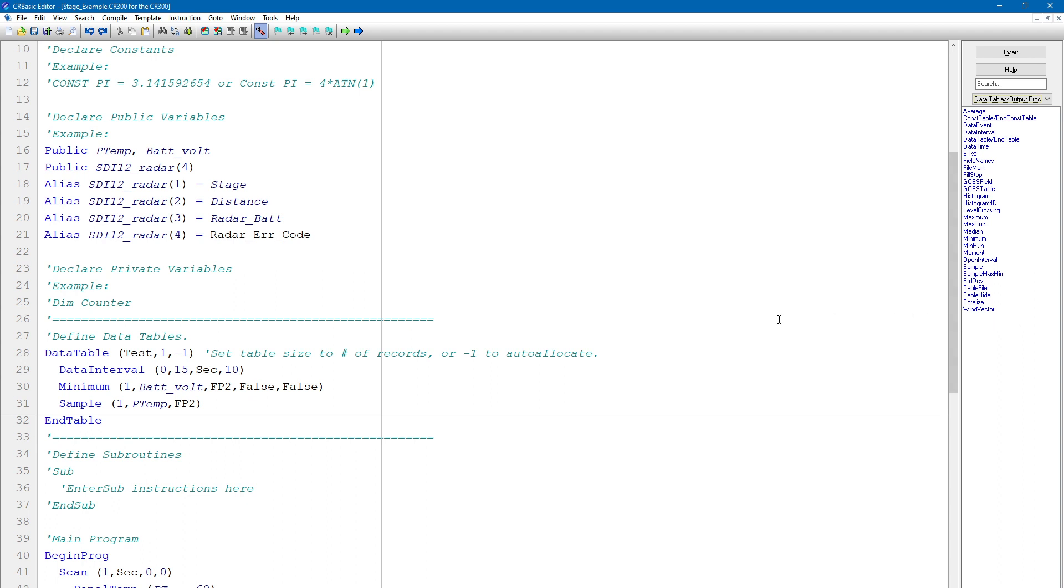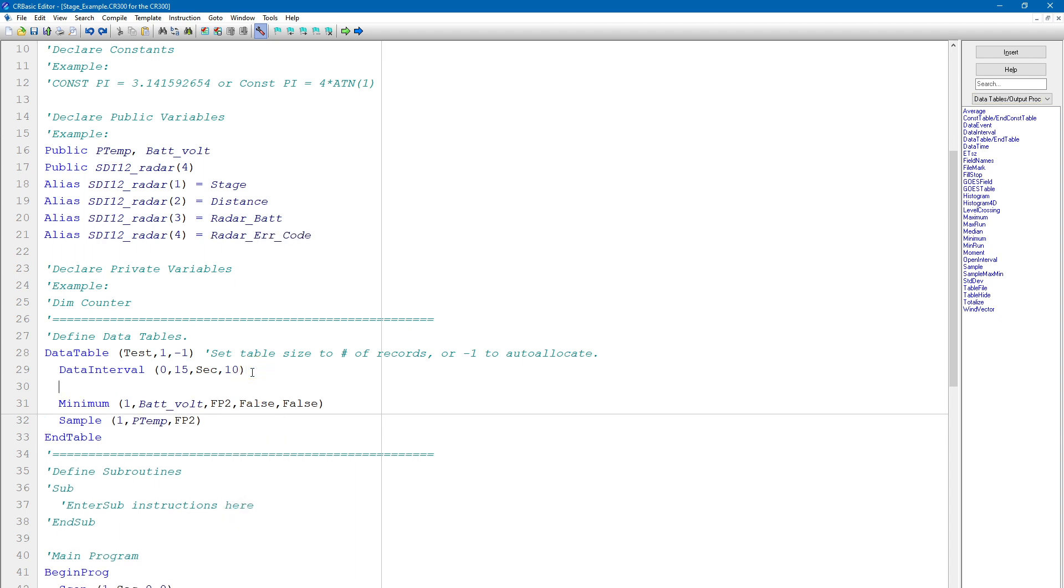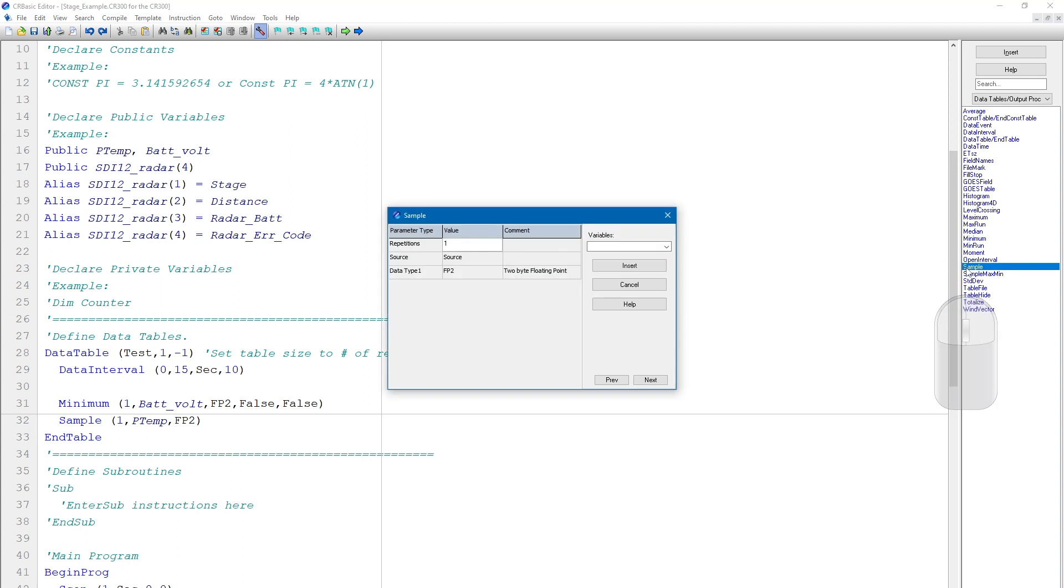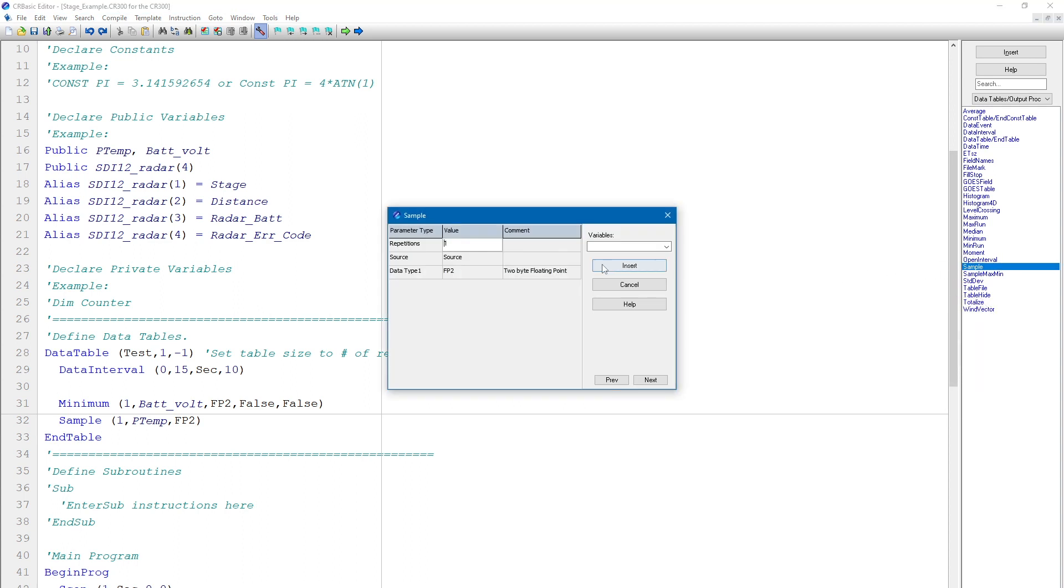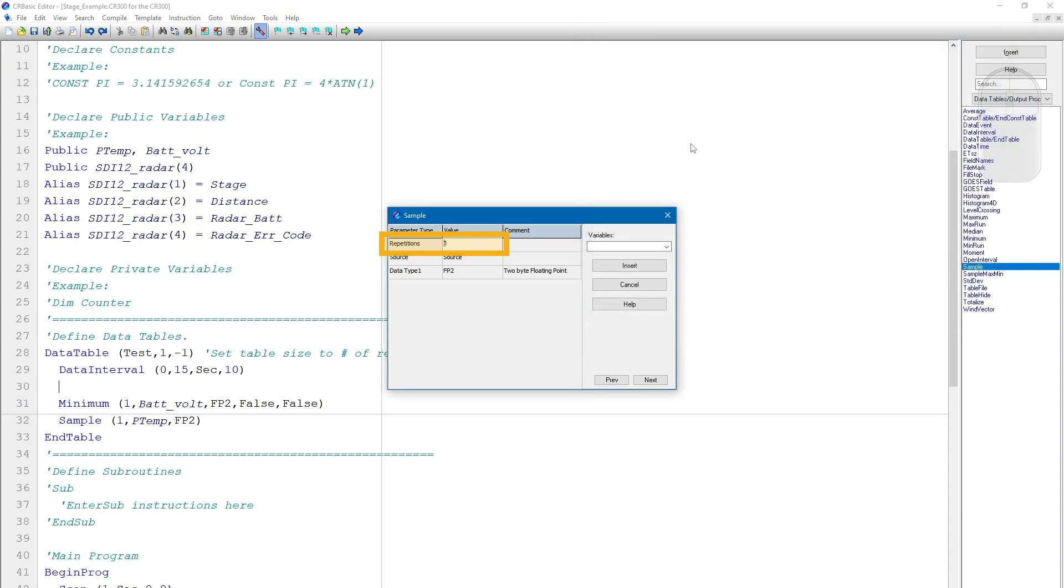So the first output I add to this data table is a sample of the stage measurement. To do this, I place my cursor where I want the sample instruction to be inserted, and then double-click on Sample in the instruction list. This opens an instruction parameter box that tells me what each parameter of the sample instruction is. I can put my cursor in a parameter value box and then use the F1 button on my keyboard to bring up help for that parameter.